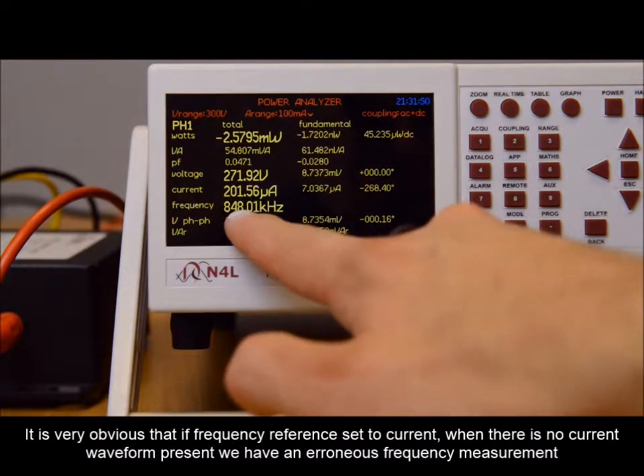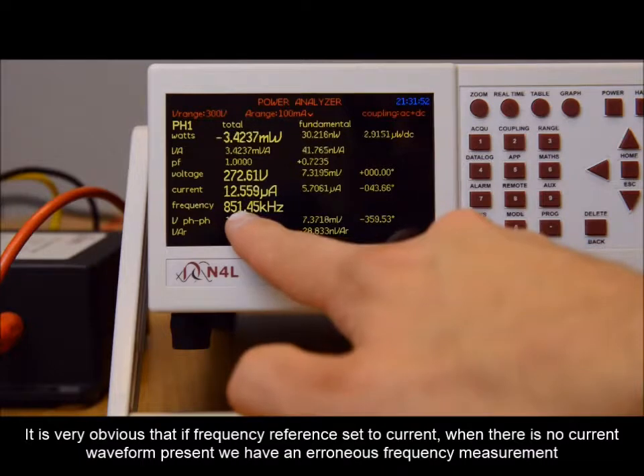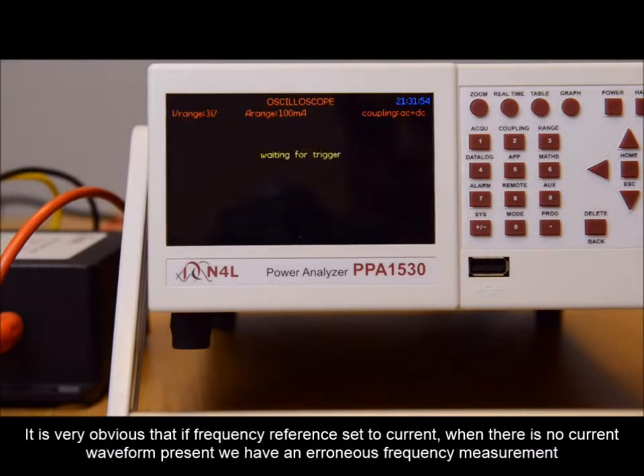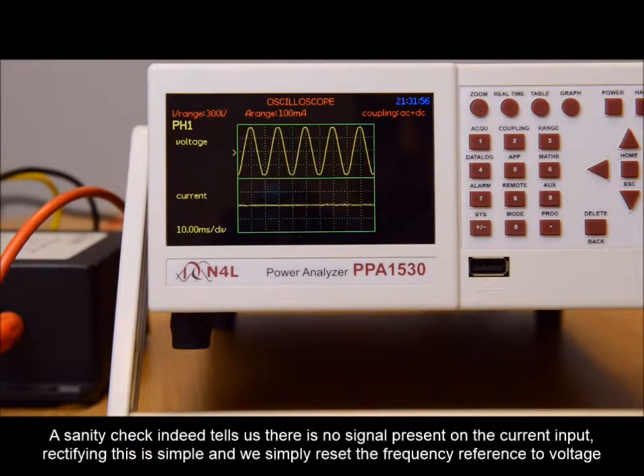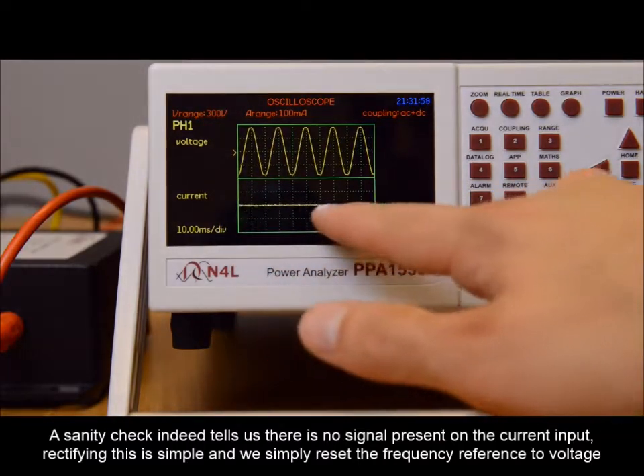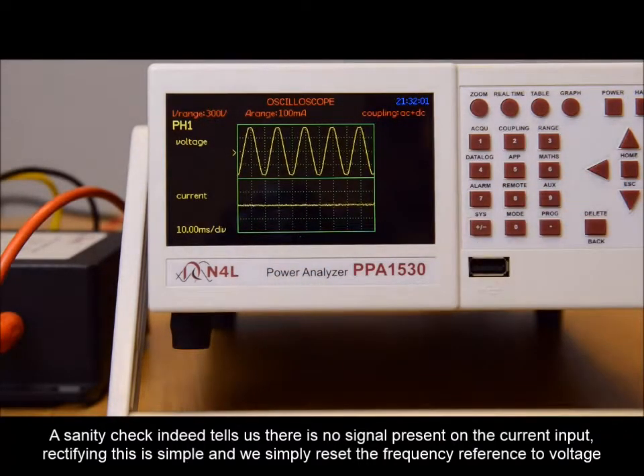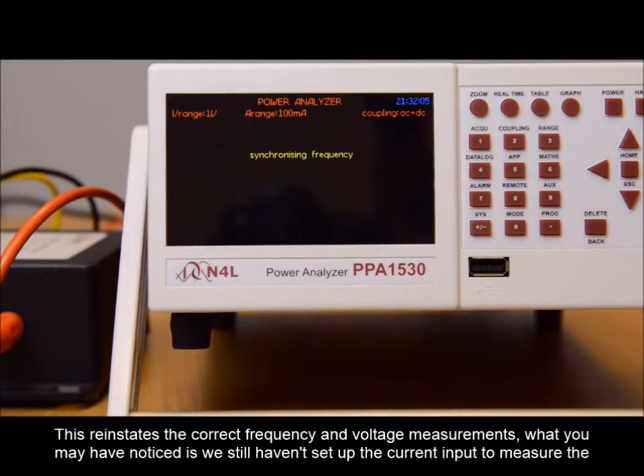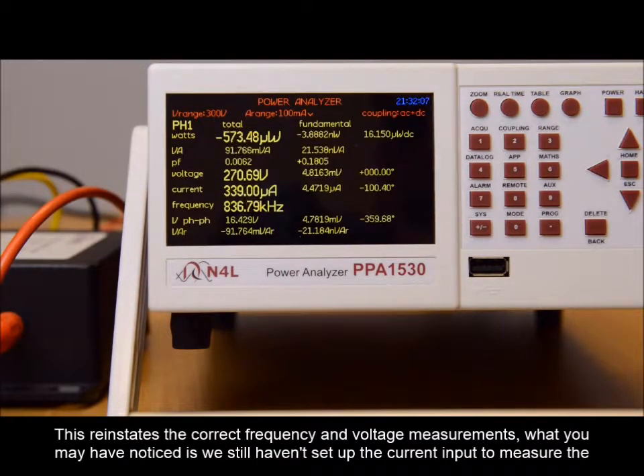It is very obvious that if frequency reference is set to current, when there is no current waveform present, we have an erroneous frequency measurement. A sanity check indeed tells us there is no signal present on the current input. Rectifying this is simple and we simply reset the frequency reference to voltage. This reinstates the correct voltage and frequency measurements.